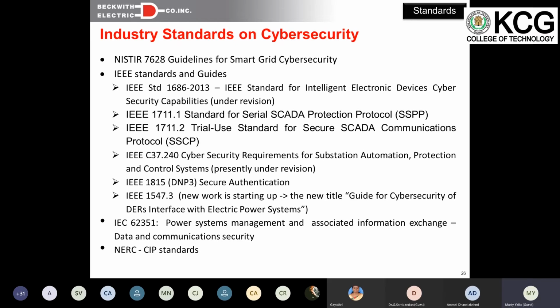And you have IEEE 1815. If you're familiar with DNP, that's the main protocol used in North America. In fact, very few people use 61850 in North America—you can count on your fingers which utilities use it. I'd say 90% of people use DNP, and a lot of power plants use Modbus. DNP does have secure authentication.